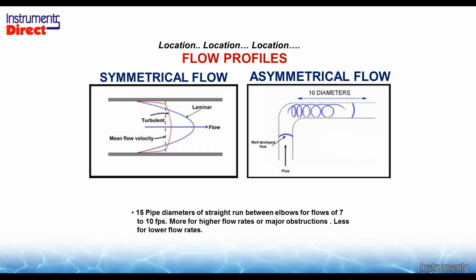So the generic rule of thumb for flow rates around 10 feet per second: after an elbow, I need about 10 pipe diameters. Put my sensor here. And then I need another 5 pipe diameters for the next elbow. If those situations occur, this is what it'll look like, and your flow meter will work at its optimum performance. Now, if I don't have enough straight run of pipe, we'll call that an asymmetrical flow profile. In this case, if I have flow going through this 90-degree elbow, notice I have a shorter distance and a longer distance. When the flow comes through this pipe, I'm going to have a tumbling effect. If I put my ultrasonic flow meter sensor right there, I'd probably get a fault condition or no information at all. I need to move downstream the 10 pipe diameters and put my sensor here, and now I will see a symmetrical flow profile.